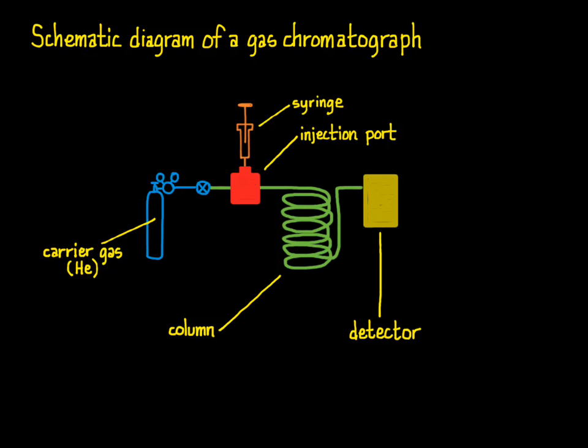The basic parts of a gas chromatograph are the column, either a capillary or a packed column, a heated injection port where a syringe is used to inject a sample through a sealed gasket into a stream of the carrier gas. It's heated to a sufficient temperature to immediately vaporize the sample. There is a source of the carrier gas and a flow regulator. At the outlet of the column is a detector that can sense a material and convert that to a signal for a computer to record.